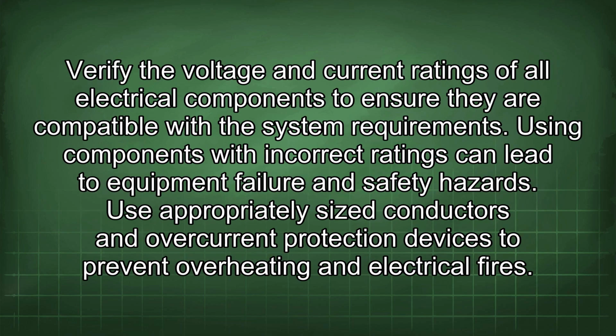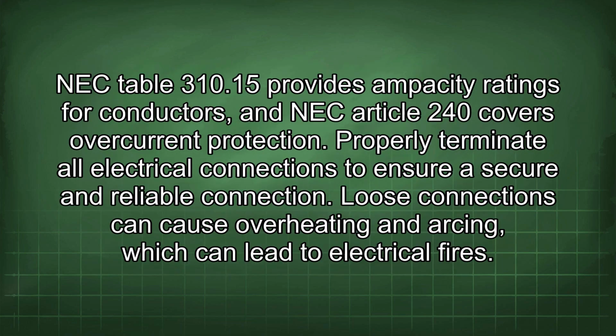Verify the voltage and current ratings of all electrical components to ensure they are compatible with the system requirements. Using components with incorrect ratings can lead to equipment failure and safety hazards. Use appropriately sized conductors and overcurrent protection devices to prevent overheating and electrical fires. NEC Table 310.15 provides ampacity ratings for conductors, and NEC Article 240 covers overcurrent protection.